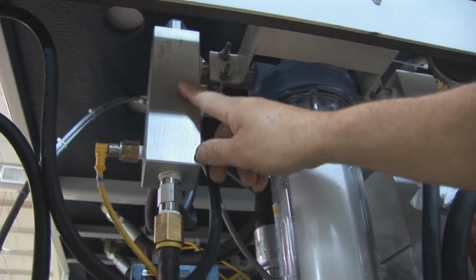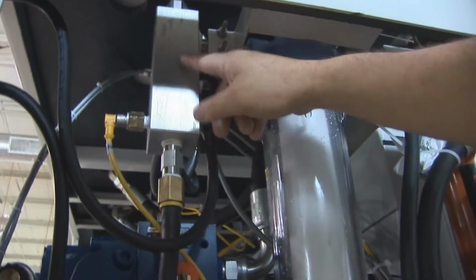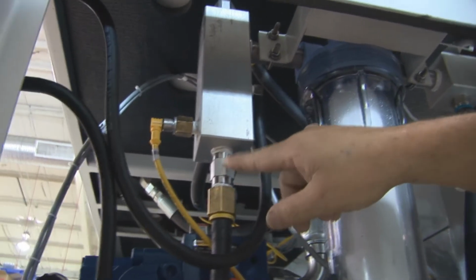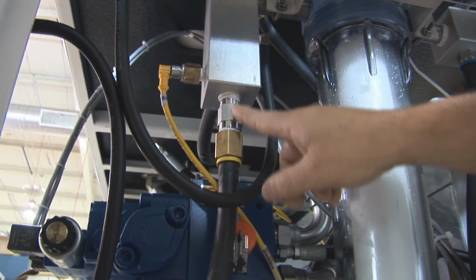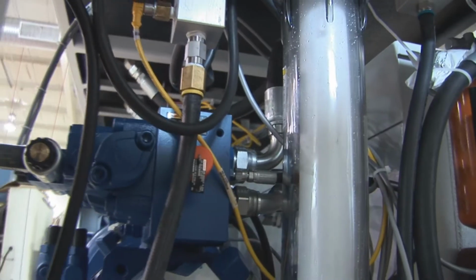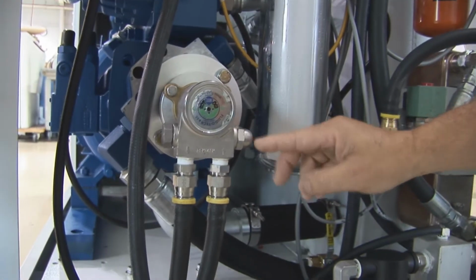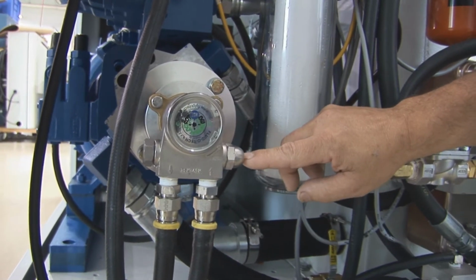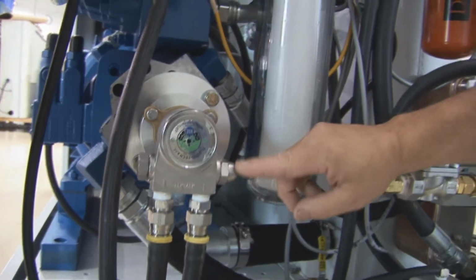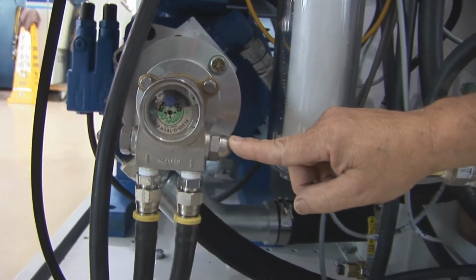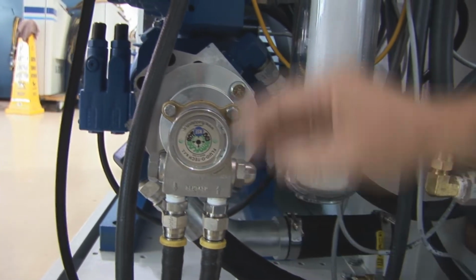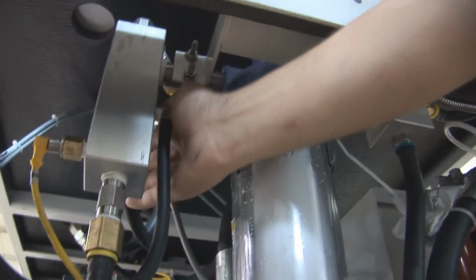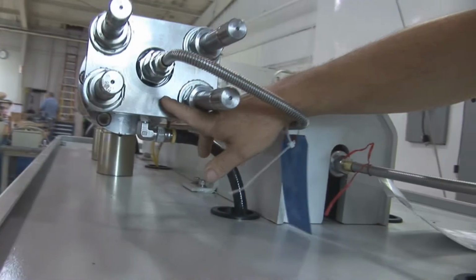You have your 60 psi switch in the back side of the manifold. You also have a relief valve. If you overpressurize the booster pump over 125 psi, water is going to be bleeding through here out to the drain. The adjustment for the booster pump is on the acorn nut right here. Screwdriver slot, turn it clockwise to increase, counterclockwise to decrease. That's the low pressure side, and then from there, when your boosted water comes through these hoses in the back, that comes up here to your check valves for your sealing heads.